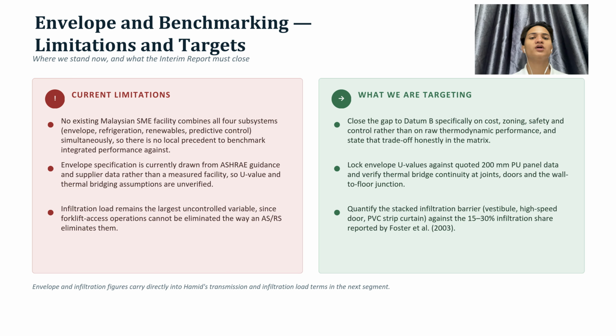Before I hand over, I want to be honest about where we still have work to do. Right now, no cold storage facility in Malaysia combines all four things we are proposing: good insulation, our refrigeration setup, solar and battery, and smart control all together. So we do not have a real local example to directly compare our whole system to. Our wall insulation numbers are also based on supplier information and standard guidelines for now, not from a real building we measured. And the amount of cold air that leaks out every time a door opens is still the hardest thing to control, because forklifts need to go in and out.